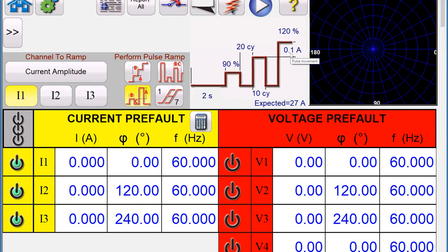We're going to increment up 0.1. Then we're going to go again 0.1. And you'll see that here in a minute. Also, we have to have some type of stopping value. So we can't just let this thing run all day long and let it just keep going. We have to stop it because at some point you have to decide, well, is the relay going to work? Is the test messed up? What's happening? And so we need to go ahead and set that parameter.